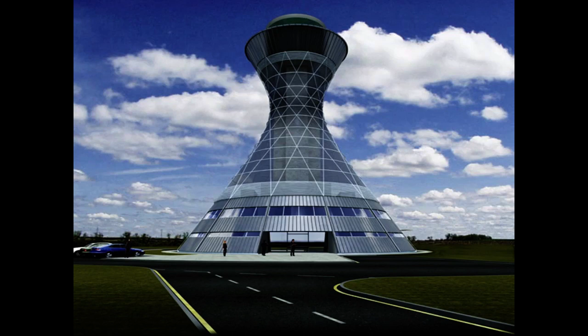The airport has backup generators across the site, including in the tower, and UPS on almost all key systems. NATS has UPS and backup generation in all of their control centres. However, it's very likely that UK airspace would be closed in a 3 to 5 day scenario, because it's safer to keep an aircraft on the ground than to have it in the air.